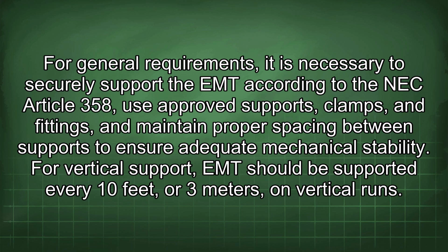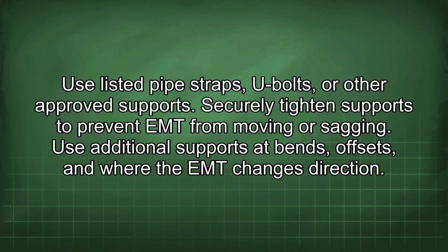use approved supports, clamps, and fittings, and maintain proper spacing between supports to ensure adequate mechanical stability. For vertical support, EMT should be supported every 10 feet, or 3 meters, on vertical runs. Use listed pipe straps, U-bolts, or other approved supports. Securely tighten supports to prevent EMT from moving or sagging. Use additional supports at bends, offsets, and where the EMT changes direction.